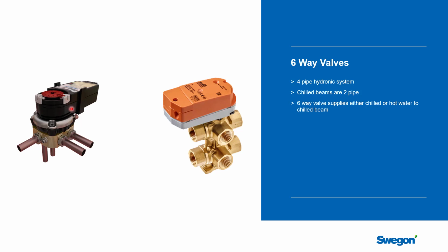Nice thing about doing this in like a hotel room application is that actually in a more temperate climate, heating can be one of the more dominant loads. And when you use a six-way valve, you can get a lot of heating capacity out of it, which I'll show you here in a second. So this is a valve from, I'm sure you'll recognize the Belimo. It's a larger one, so if you're doing a larger control zone and you had 5, 6, 10 GPM of flow going through it, this valve is more than capable of doing that.